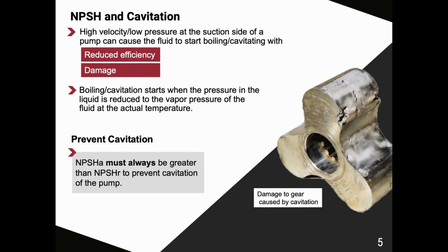It doesn't sound good, and you can tell there's definitely something wrong. I mean, John, have you heard? I've heard pumps cavitate, and it gets pretty loud. It sounds like there's some hammering going on inside that steel pump, and if it's making a lot of noise, people want to head for the door. Yeah, and especially if you're at a high-end hotel, any excess noise is not appreciated.